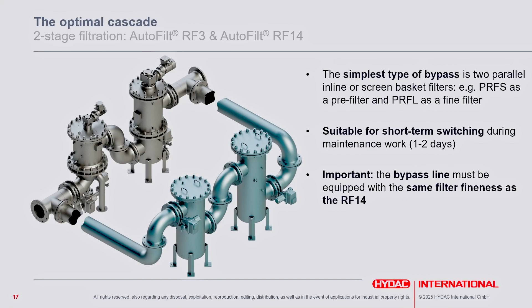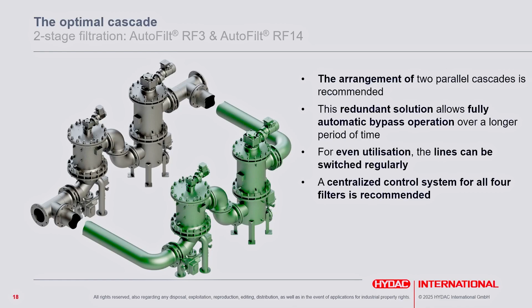One other way, which is pretty typical, for example, in hydropower, is to build up a redundant system with 2 lines, and in each line we have our backflushing systems. This redundant solution can be operated fully automatically with the help of one centralized control. And for even utilization, the line can be switched regularly. For example, 1 day line A, 1 day line B, and so on. This may be one solution for your customer. When you have a specific application, come back to us and we talk together and find solutions together how to propose a system for your customer.